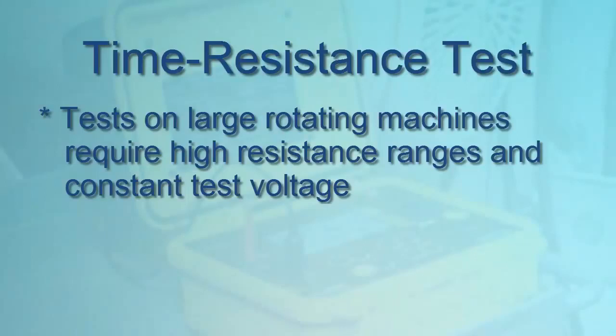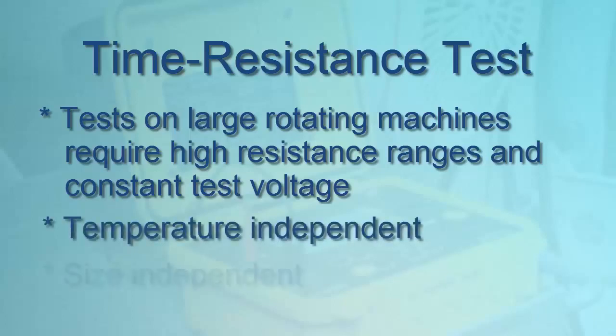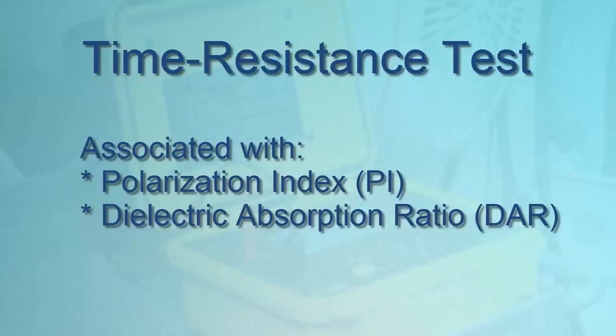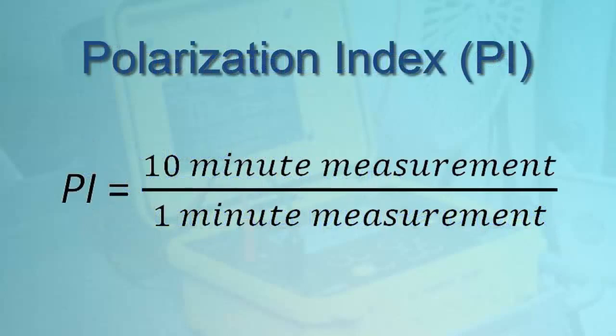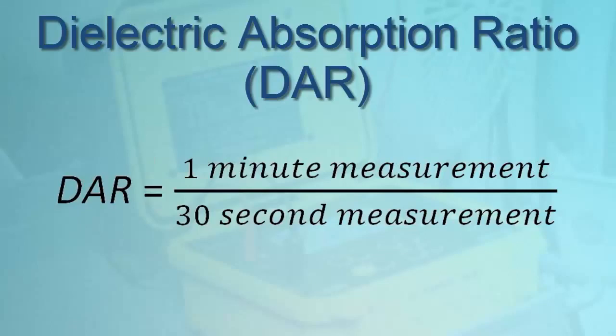Time resistance tests on large rotating electrical machinery, especially systems with high operating voltage, require high insulation resistance ranges and a very constant test voltage. Since this test provides meaningful results within a single 10-minute duration, it is relatively independent of temperature and also independent of the size of the system under test. The time resistance test is sometimes associated with two values: the polarization index, or PI, and the dielectric absorption ratio, or DAR. The PI is derived by dividing the 10-minute resistance measurement by the 1-minute measurement. The DAR is calculated by dividing the 1-minute measurement by the 30-second measurement. Although DAR is no longer commonly used with new insulation systems, it may still have applicability when testing older insulating materials.